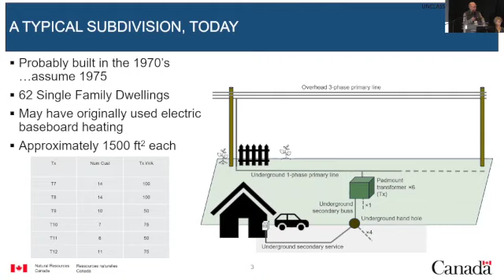One thing I didn't tell you was about the standards. If I'm handed a drawing of a subdivision—a road with a bunch of lots—I'll ask questions: what kind of homes will be built, what's the heating source, and what's the square footage. Those factors feed into the standards to create a point system. The points are added up, and that number defines the transformer size, all based on load profiles modeled in the past to make it easy to design a subdivision.